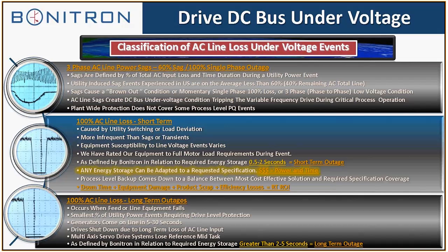We can also provide servo drive protection too. There's no difference to Bonitron as far as a servo drive DC bus and a VFD DC bus. So usually with long-term outages, greater than 5 seconds, we start talking about batteries, using batteries. So the two main energy storage devices we use are capacitors, either electrolytic or ultracapacitors, and batteries.